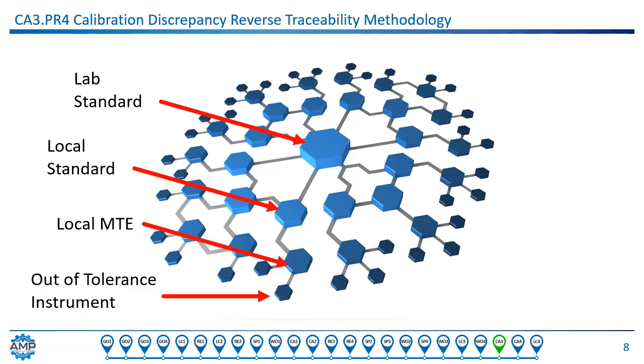When the standard is suspect, it peels back a layer of confidence in the calibration program. The standard of interest might have been used in a lot of places since it was calibrated to the next higher standard. Now there's a ripple effect. Now every instrument tested by this standard is suspect if it was calibrated while the standard may have been out of tolerance. If the standard is a commercial lab doing thousands of calibrations, the ripple effect could have tsunami proportions. This can be an administrative nightmare, hence the need for a process to accomplish it effectively.